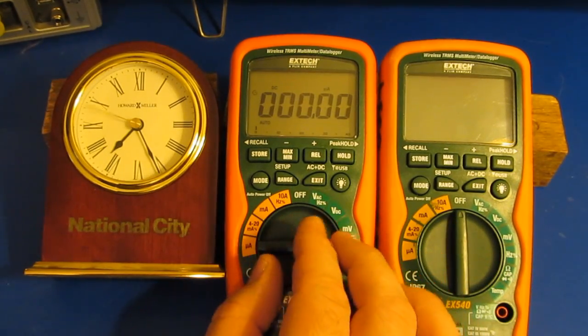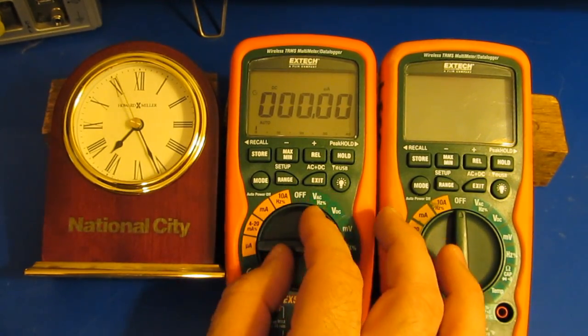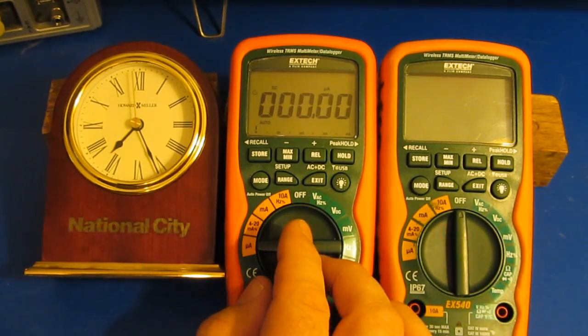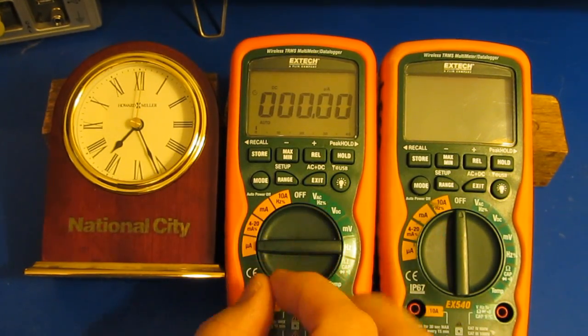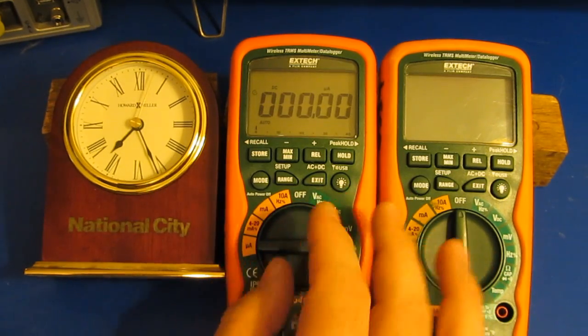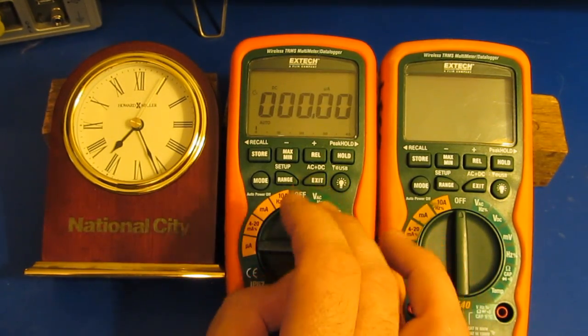Once I took the selector switch apart, I noticed that one of the contacts resting heights was a little bit lower than the other five. And I used an exacto knife to thin down some of the plastic and that seems to have corrected that problem.